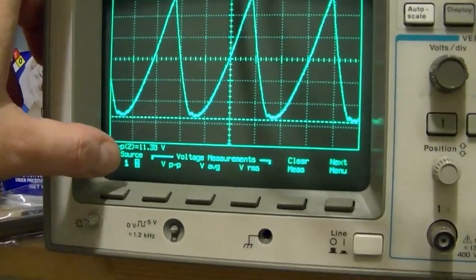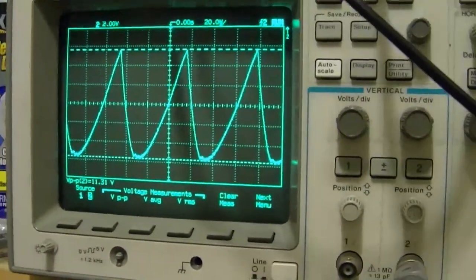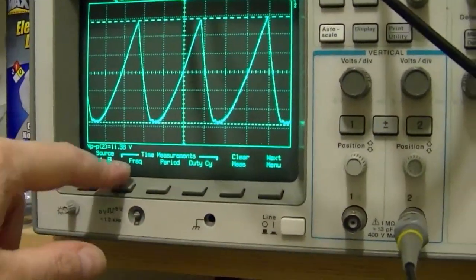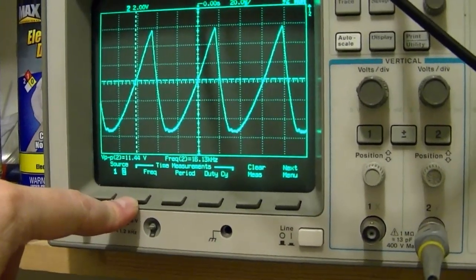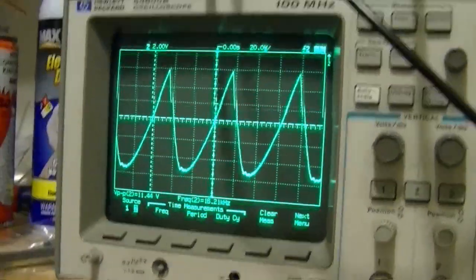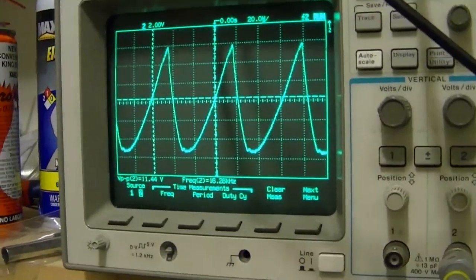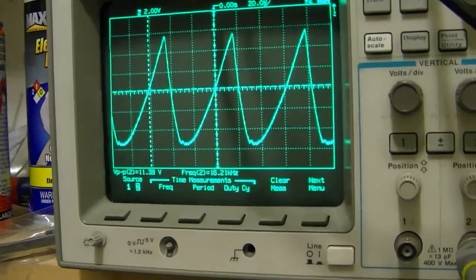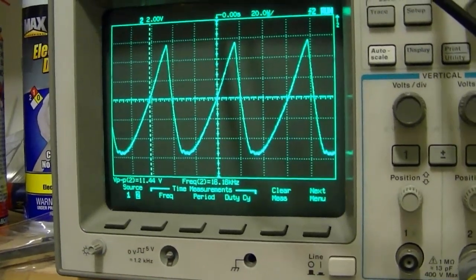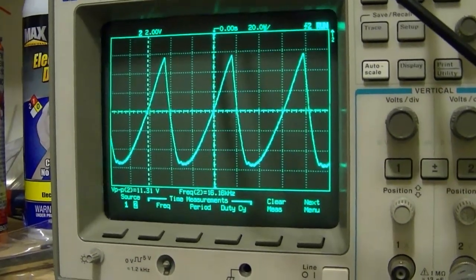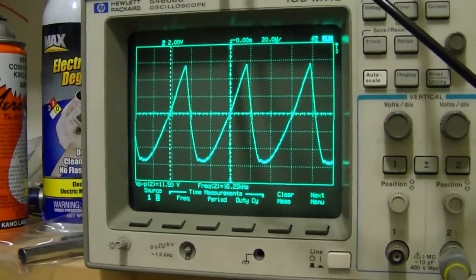11.4 volts peak to peak. That's pretty darn close. Let's double check the frequency, which should be lower than that, should be 15.75 kilohertz. I've got about 16 and change. So although the amplitude's right, the frequency's off.